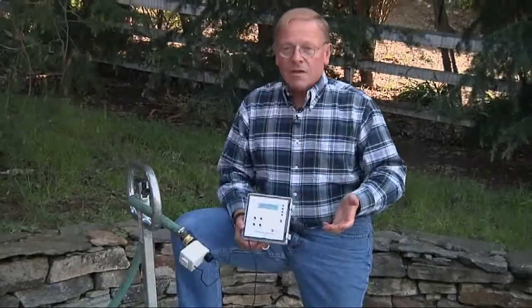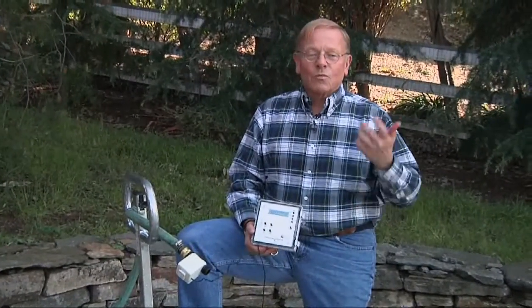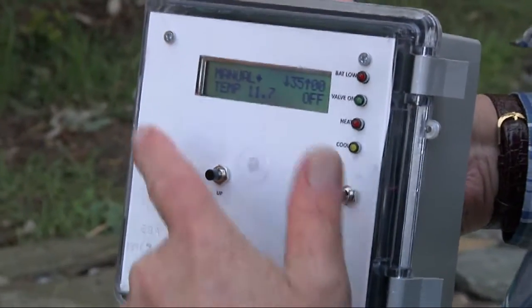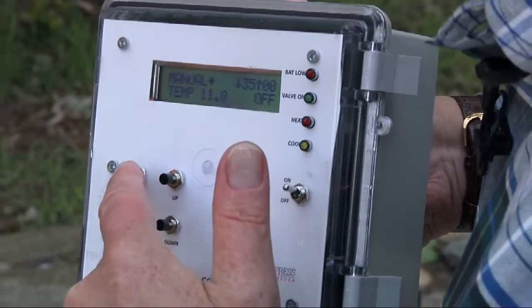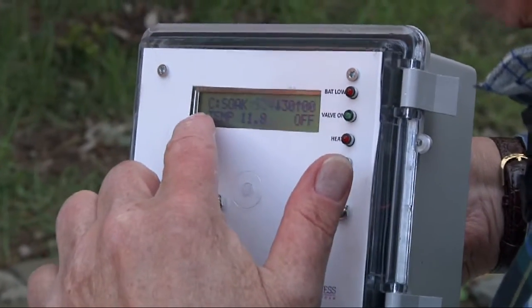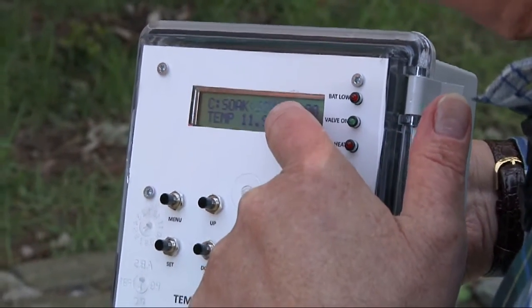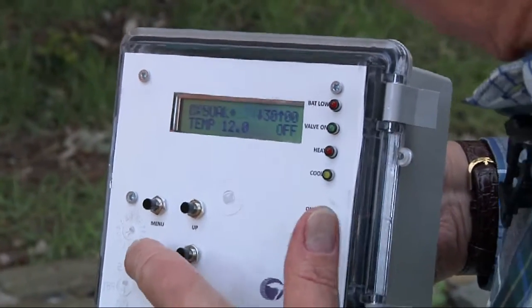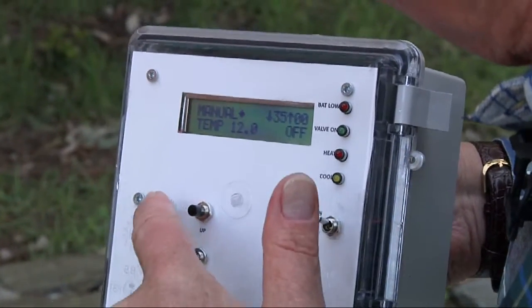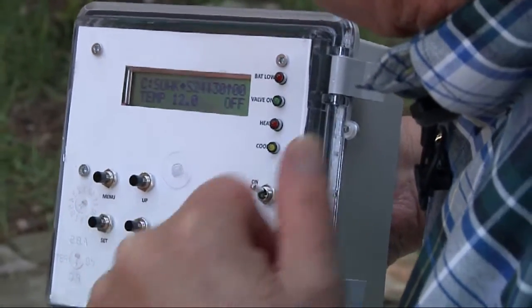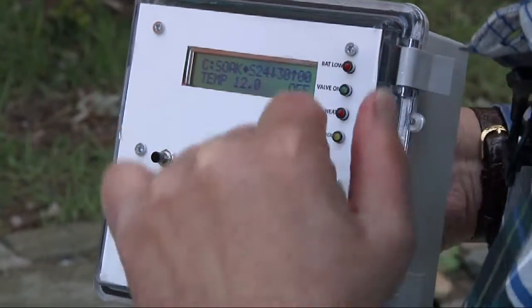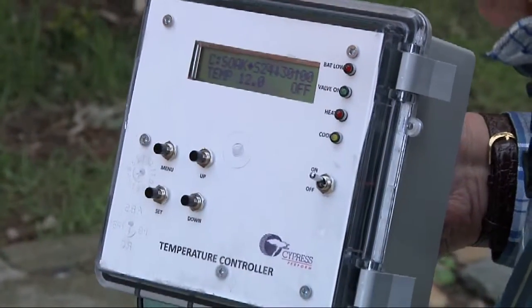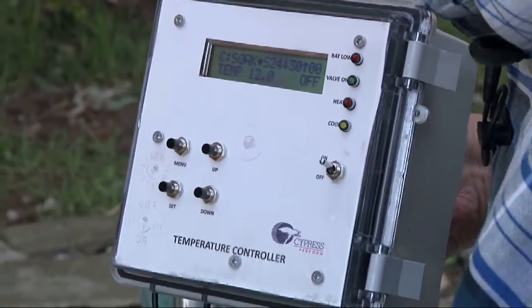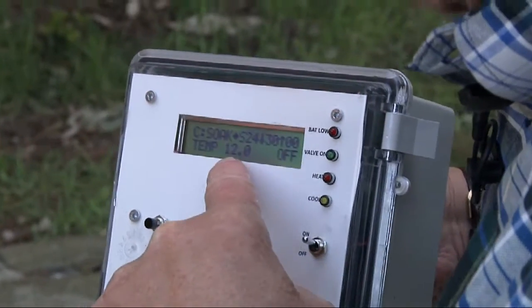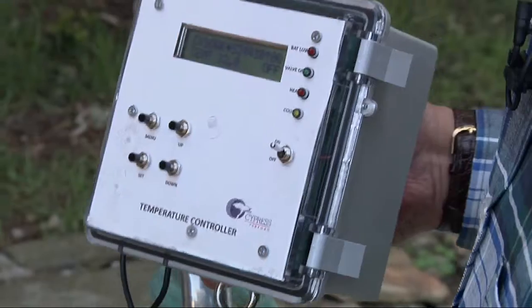Now, how do you control it with temperature? I'll go to the menu and change the mode. There are 7 modes, only 2 of which I'll explain. I'm going to cold soak mode, with a set point of 24 degrees centigrade. I'll set the set point to 24 degrees centigrade. Now the thermistor controls the valve. The thermistor currently reads 12, and since the set point is 24, it's colder than the set point, so it doesn't care.